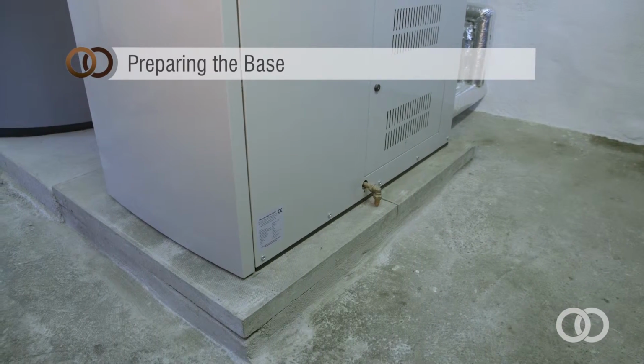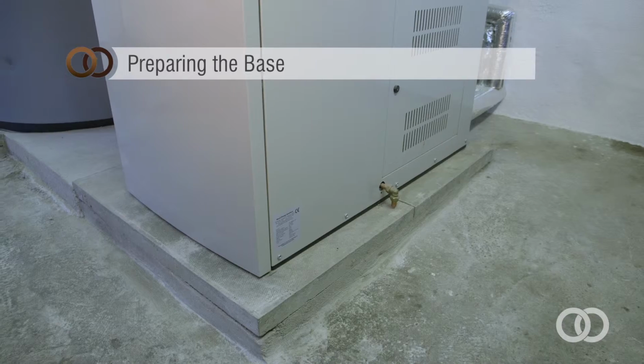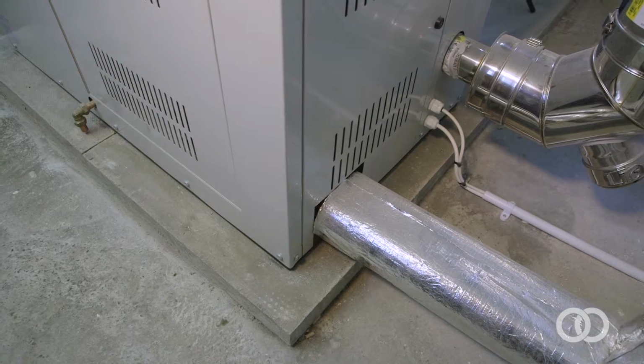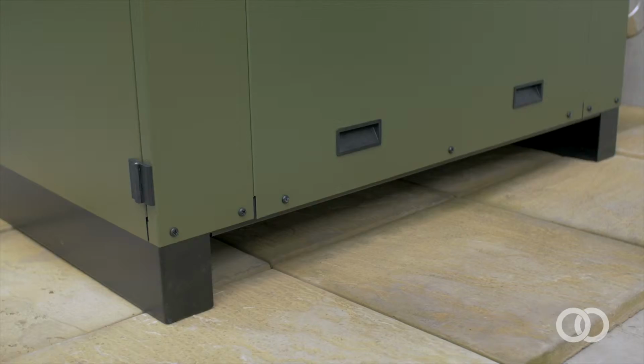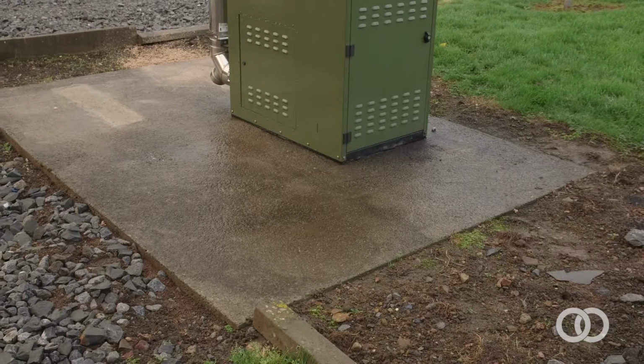Preparing the base. For internal boilers, there is already likely to be a non-combustible concrete or tiled base in the plant room where the unit is to be placed. For external boilers, it may be necessary to install a base.